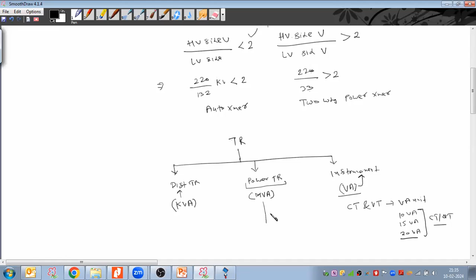Now, the next point: this power transformer, again we can divide. I am dividing based on the use, not based on the cooling medium, but based on the application. Based on the applications, I have divided into three. In substations, we use all three types of transformer: one for the auxiliary supply, one for power transmission, and one for metering and protection purposes. So all three are used in substations.